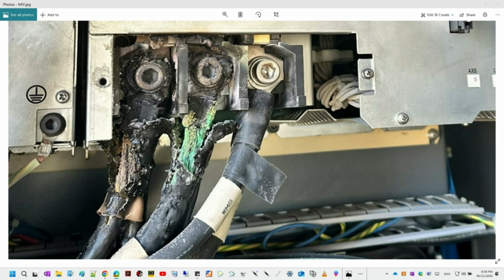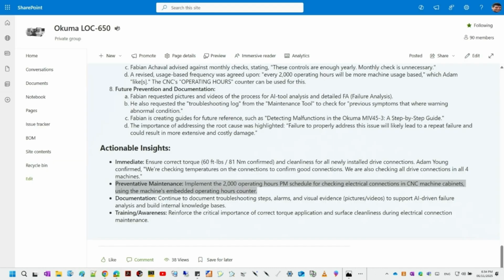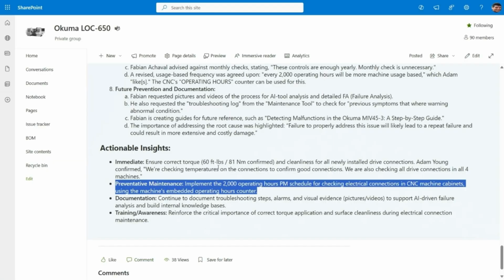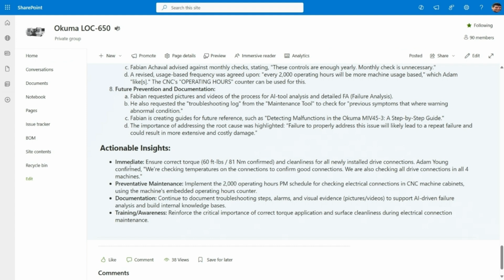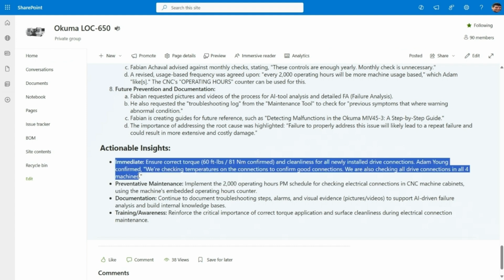And the sources were very clear on the specific crucial steps recommended to prevent this exact type of high-resistance failure. First, ensure proper torque. Always use a calibrated torque wrench, and tighten those terminal bolts precisely to the manufacturer's specifications, which you'd find in the Okuma maintenance manual. They mentioned the value they used for the replacement, right? They did. They noted that during the replacement, they torqued the new connections to 60 foot-pounds, which is about 81 newton meters. Having that specific value is key. So using the right tool on the right spec is just non-negotiable.